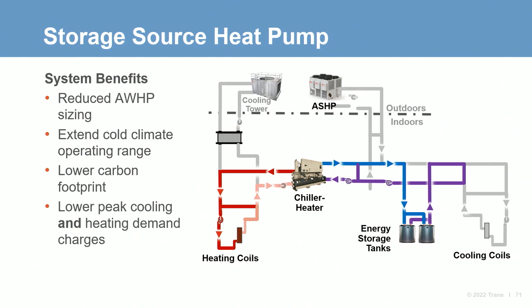In this chiller heater system, heating loads are served by a water-to-water heat pump that can source energy from the building, the air, or from the energy storage tanks. In turn, the energy storage tanks can collect energy from the ambient air using the air-to-water heat pump, they can reclaim energy from the building, and can dispatch energy when they are used as a source for the chiller heater.